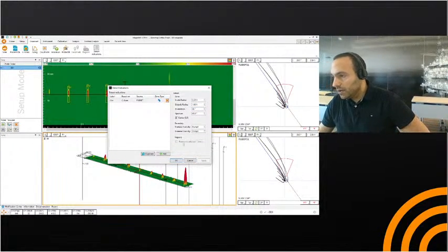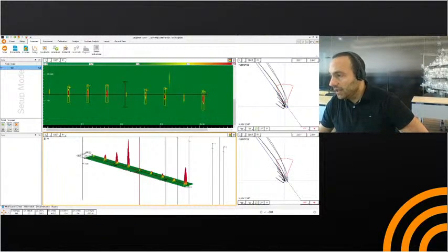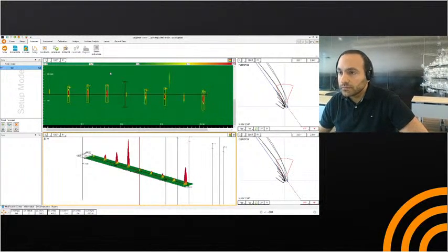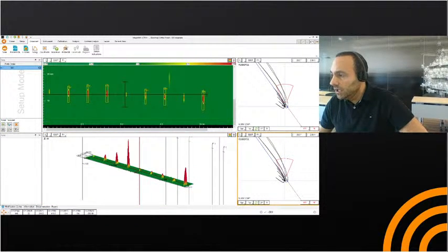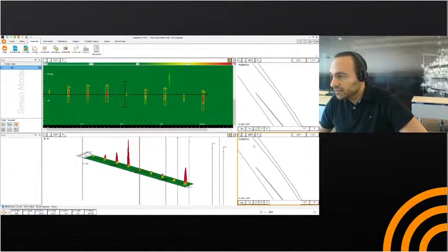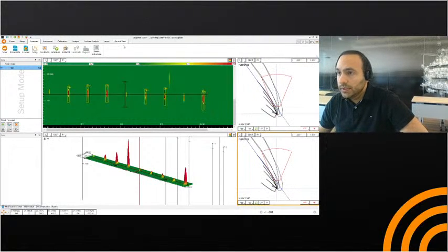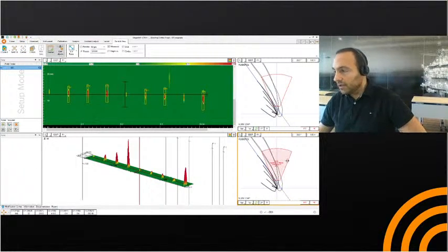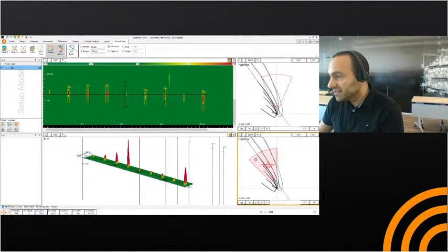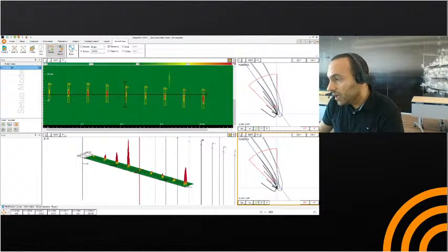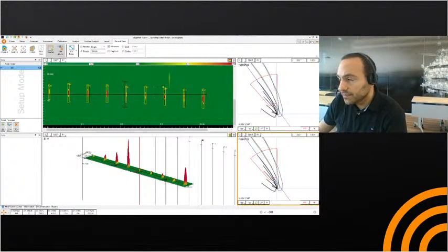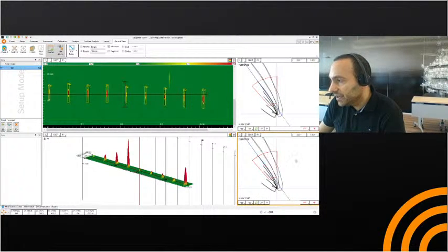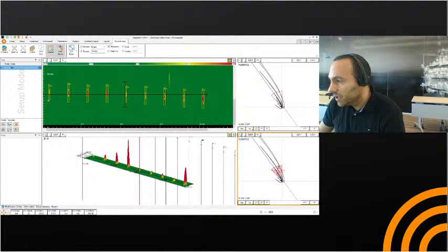So you can see how we have an alarm box, we call it, in the Lissajous view, and we are able to adjust it. So you just need to, if I go back, go to current view, edit alarm, you can see how I'm able to focus only on my defects that I'm getting here. If you zoom out, you can have a bigger one here.